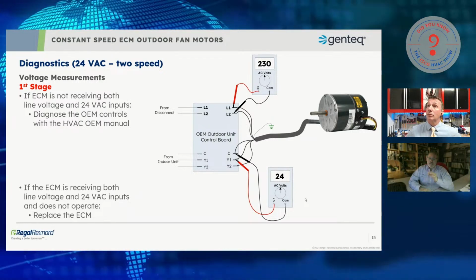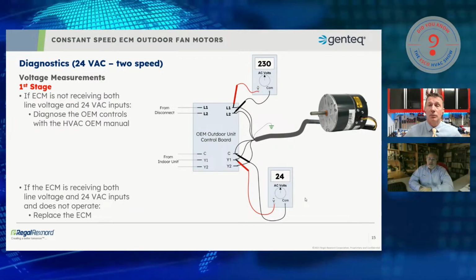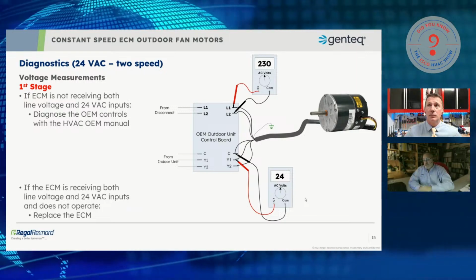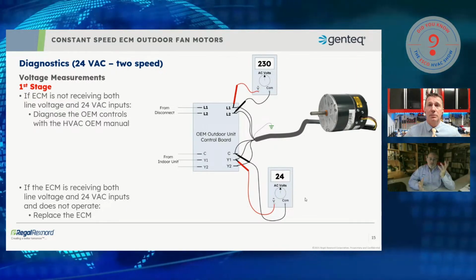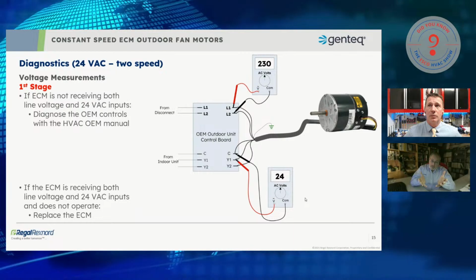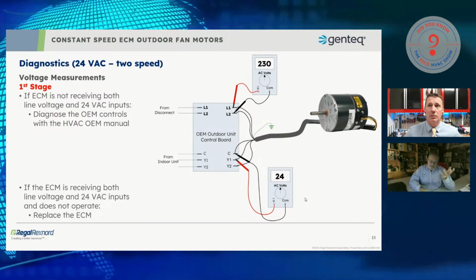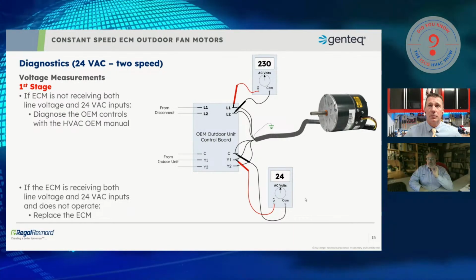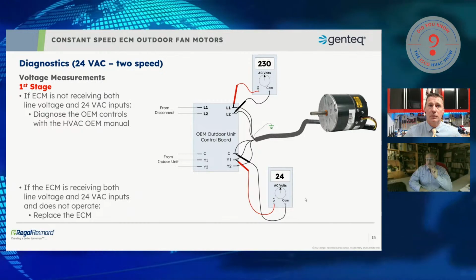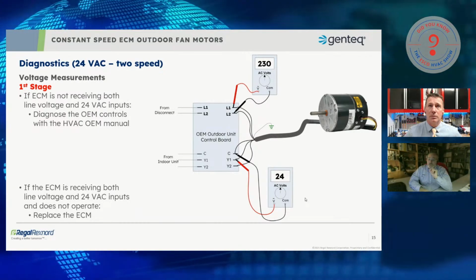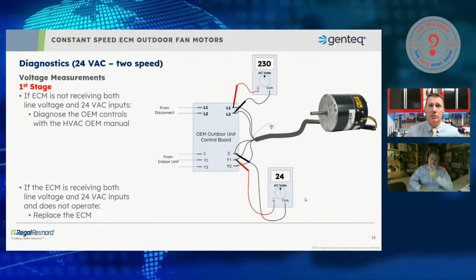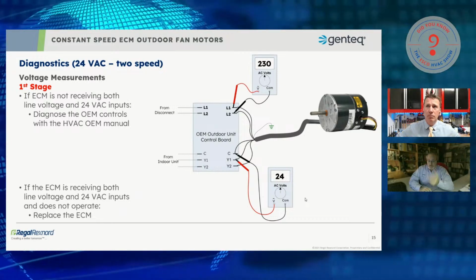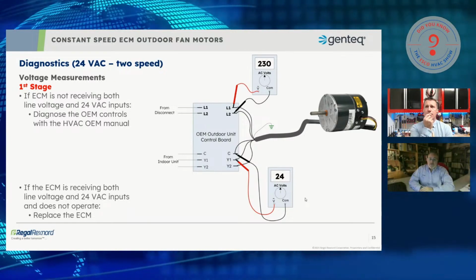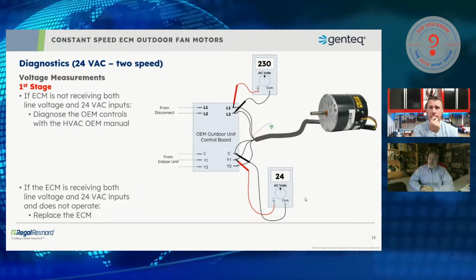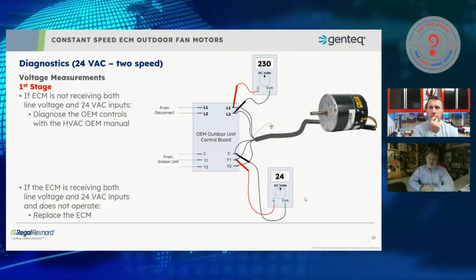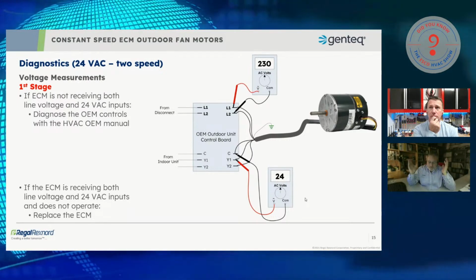So if I'm in second stage compressor, but my motor's only operating on first speed, maybe the wire fell off of the Y2 there. Who knows why the second speed didn't, or maybe the second speed doesn't work. Very rare, but possible. It's good to understand, one, is this particular system going to switch from Y1 to Y2, or is it going to energize both? And secondly, do I have the Y2 voltage on? There are technicians in the southern regions logged in right now that are probably like, this is so common sense, Chris.